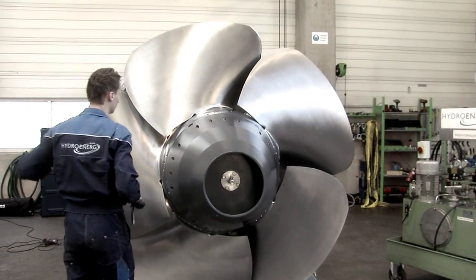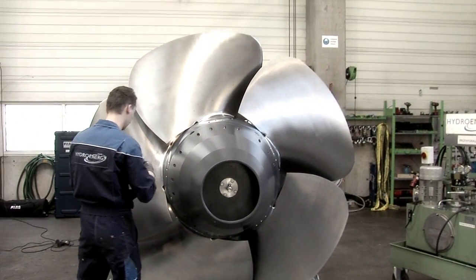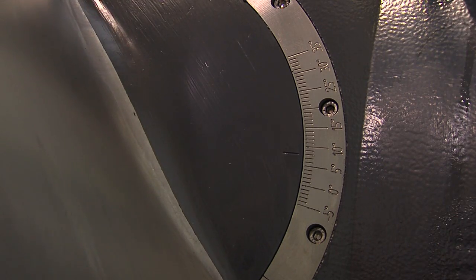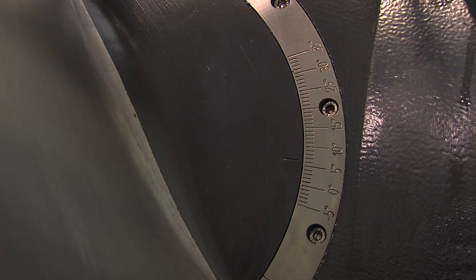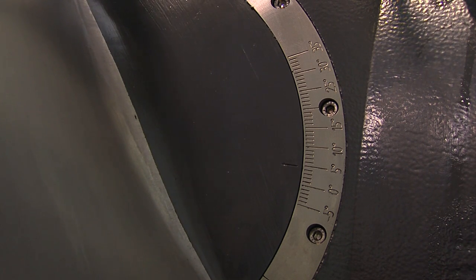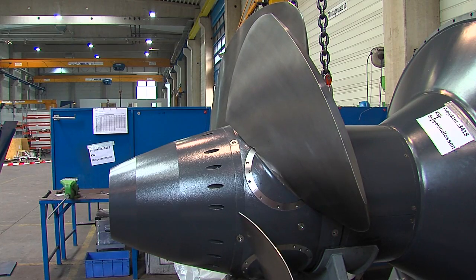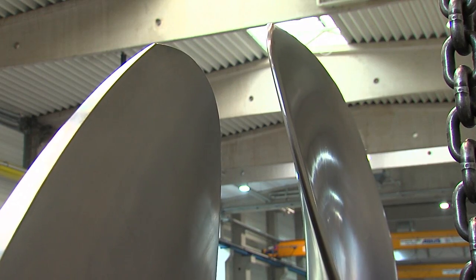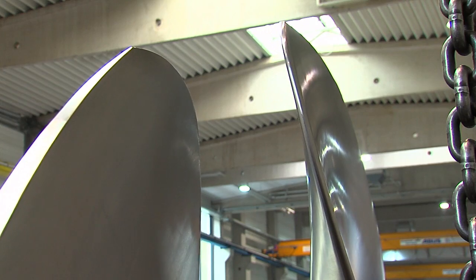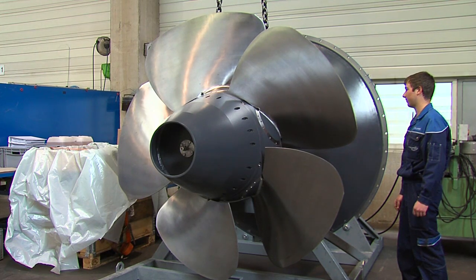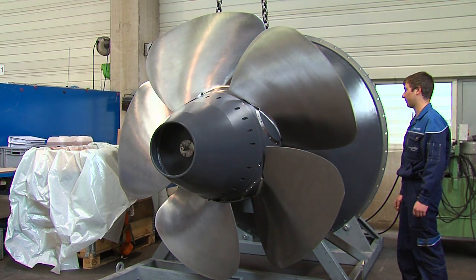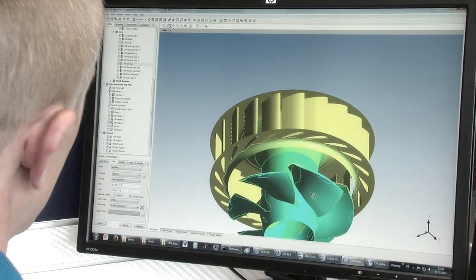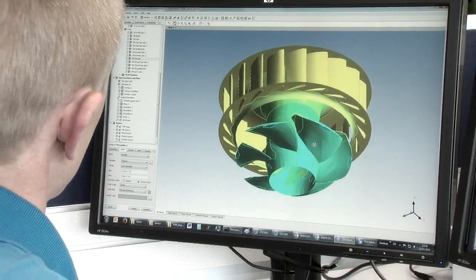Kaplan turbines are suitable for a low water head at a high water flow rate. The turbine blades and the wicket gate are adjustable. Double regulation allows the turbine to adapt to fluctuations in water flow rate and different water levels.